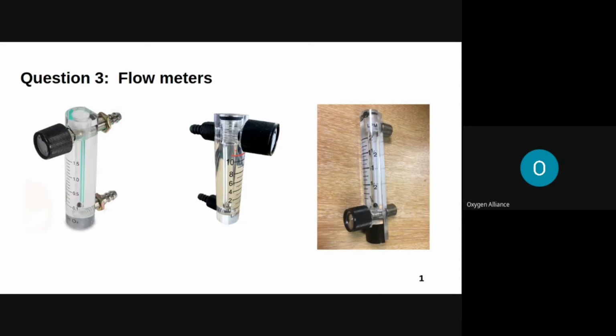So you need to look at the form factor of the flow meter. This is basically the physical look of the flow meter. It needs to match the size of the original flow meter. This is in terms of width, height, and the position of the inlet and the outlet port. So if you could go to the next slide.